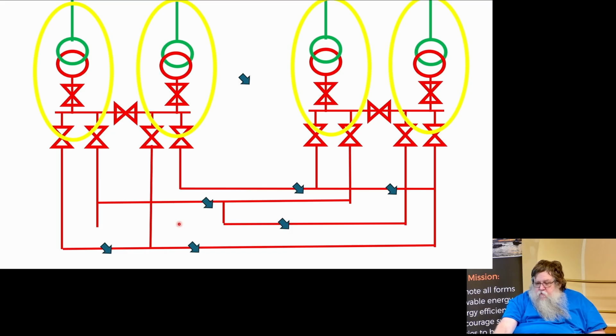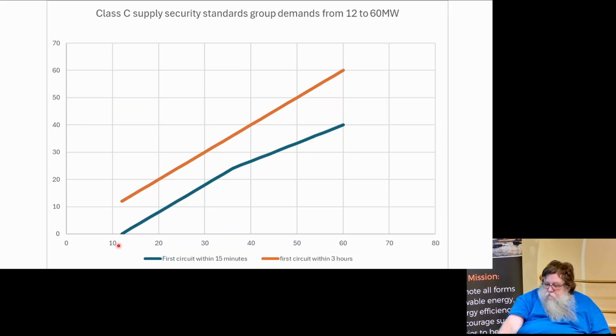Sometimes we get faults that affect more than just the transformer. So in this case, if one of these faults occurred, these 2 feeders would go dead, and we would have to move open points to get supplies restored. And we have to get those supplies restored to 2/3 or 12 megawatts less than the total demand within 15 minutes. But we've got 3 hours to do the rest. And that 3 hours means people going out and closing these circuit breakers. And this is just a graph showing how much you've got to do within 15 minutes and how much within 3 hours.